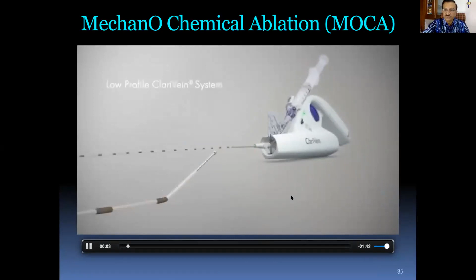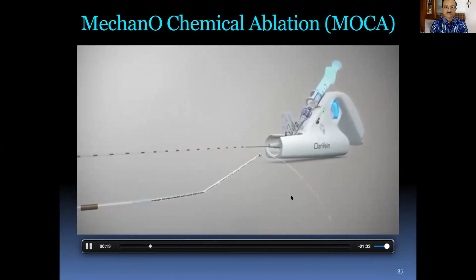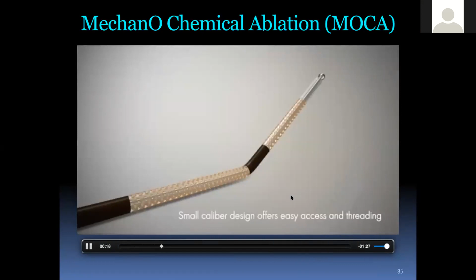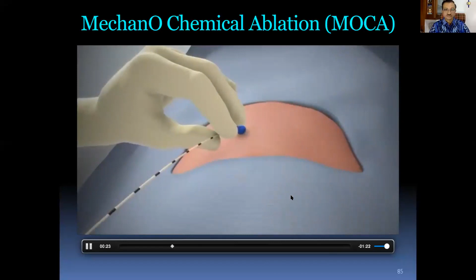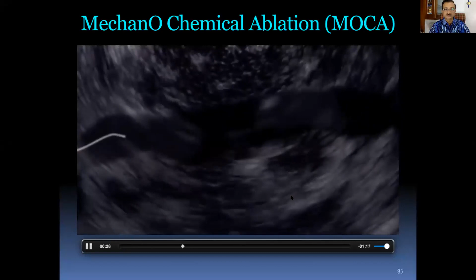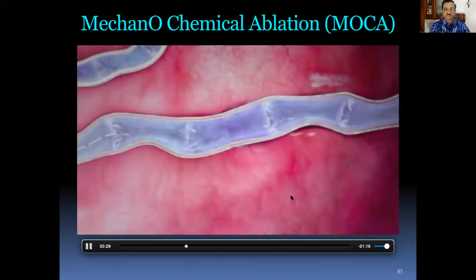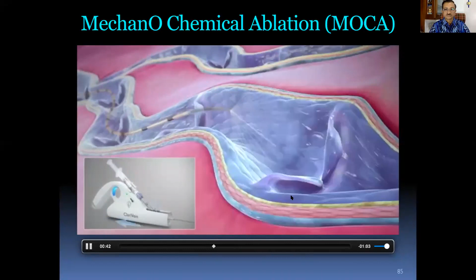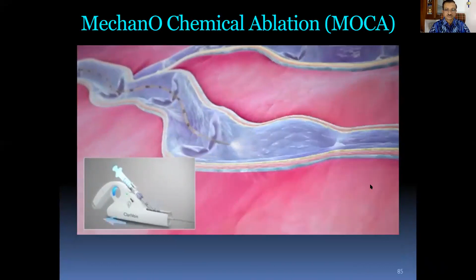Veins. The revolutionary low-profile ClariVein system combines mechanical action with the infusion of physician-specified fluid. Effectively, the small-caliber design offers easy access and threading. Typically deployed through a 4 or 5 French microintroducer under ultrasound guidance, the catheter tip shows brightly. Upon activation, the unique rotating ball dispersion tip rotates at approximately 3,500 RPM, creating a targeted penetration of liquid sclerosant, leading to vessel closure. After 2 to 3 seconds of pullback, the operator begins infusing the agent while pulling back at the average rate of 1 centimeter per 6 to 7 seconds.